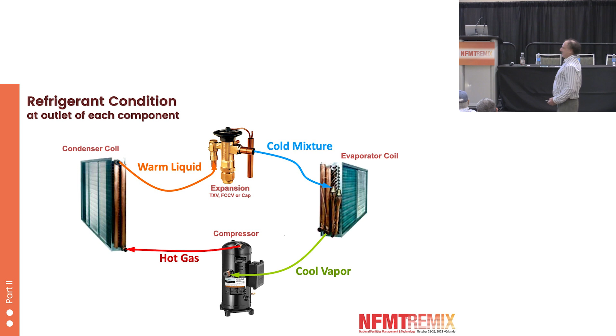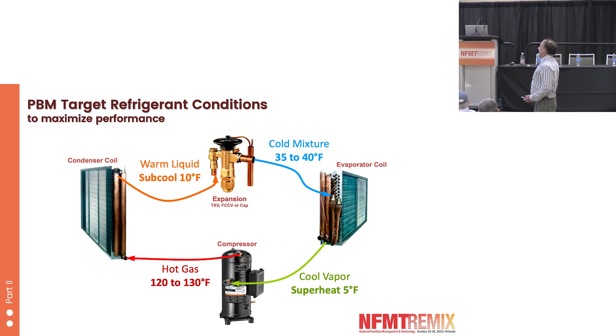But if you're trying to optimize the performance, there's ranges or target values that really give the best performance. So you can measure these things and see where you're at compared to what would be optimal and make adjustments. For example, if the cool vapor leaving the evaporator coil, the superheat, should be 5 to maybe 10 degrees for best performance, and you measure it and it's 20 degrees, the unit's still going to work at 20 degrees, but it's not going to work really great. So you would adjust the expansion valve, assuming it's an adjustable expansion valve, to try to get that down to about 5 degrees. And when you do that, usually the hot gas temperature is going to decrease too, from maybe 150, 160 down to 130-ish.